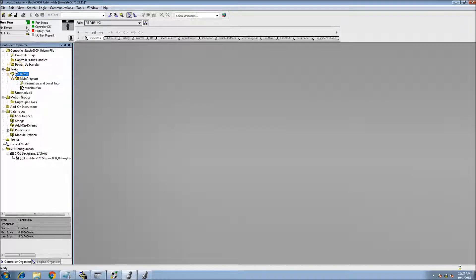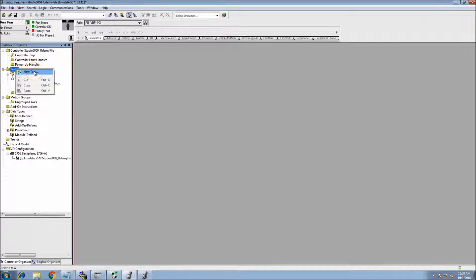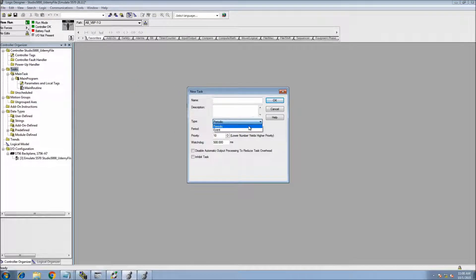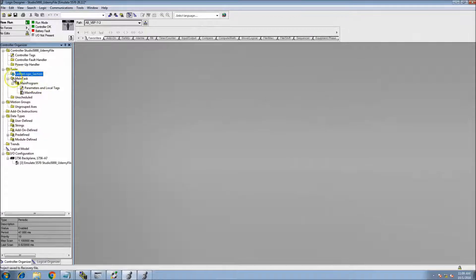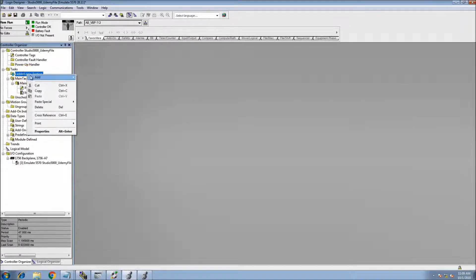Let's add a new task. We're going to add a new periodic task and call it 'Ladder Logic Section' so we can easily control where and what language we're programming in. We'll put this at 47 milliseconds — this periodic task is going to scan this routine every 47 milliseconds. Now we have that in our task, and we need to add our program.